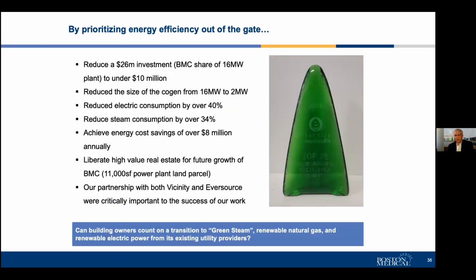Move to the next slide, please. By prioritizing energy efficiency right out of the gate, we were able to reduce the total investment in the cogeneration equipment - for BMC's share that investment was going to be $26 million, and we reduced that to under $10 million. The size of the cogen went from 15 to 16 megawatts down to 2 megawatts.